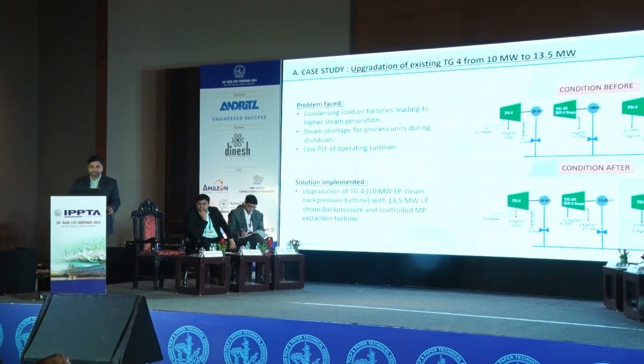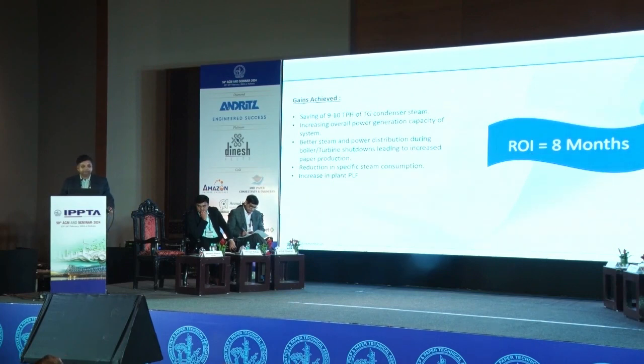Now, the solution which we implemented: we upgraded our TG4 from 10 megawatt back pressure to 13 megawatt LP back pressure and MP controlled extraction turbine. What gains have we achieved? We have been able to reduce our condensing load by 9 to 10 tons per hour. Our overall power generation capacity has increased. Better steam and power distribution during shutdowns has really helped us to increase paper production, reduce specific steam consumption and increase plant PLF. The ROI of this project was 8 months.